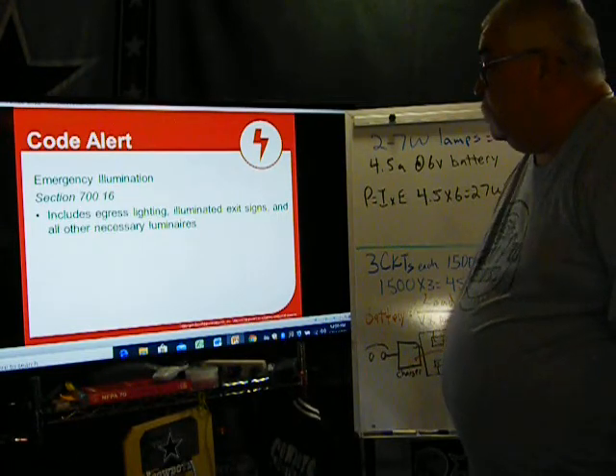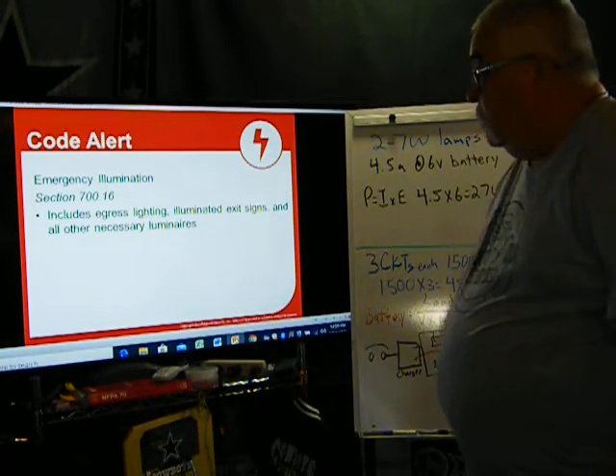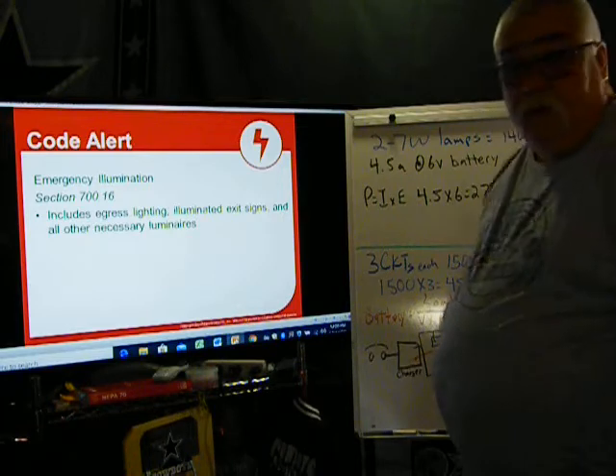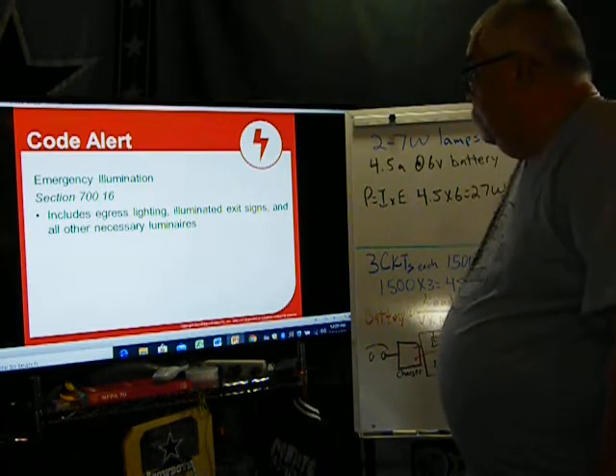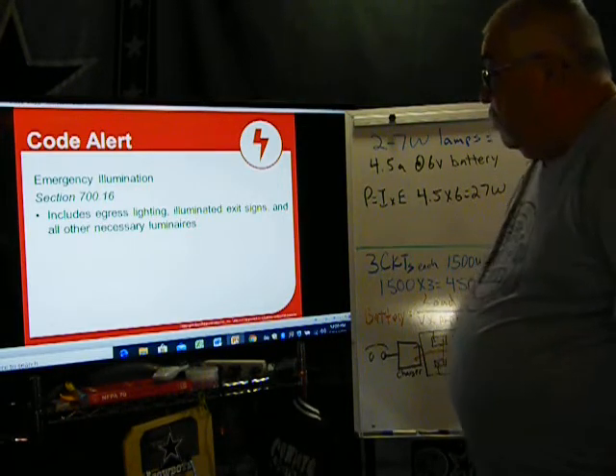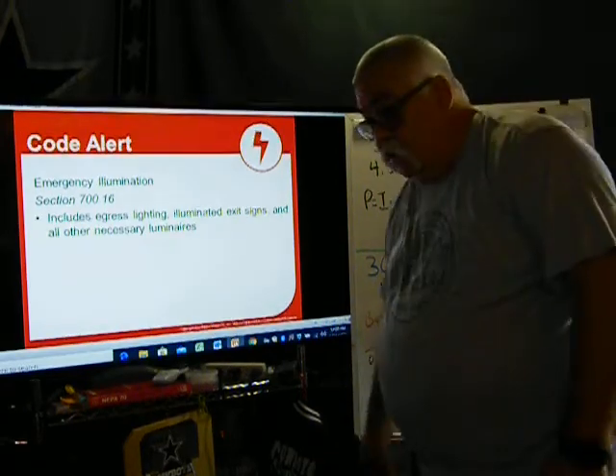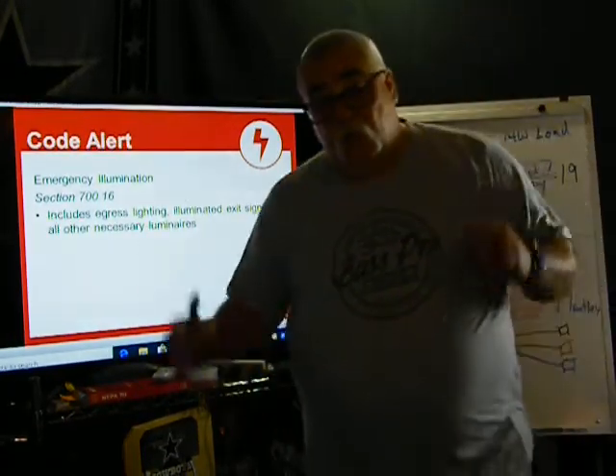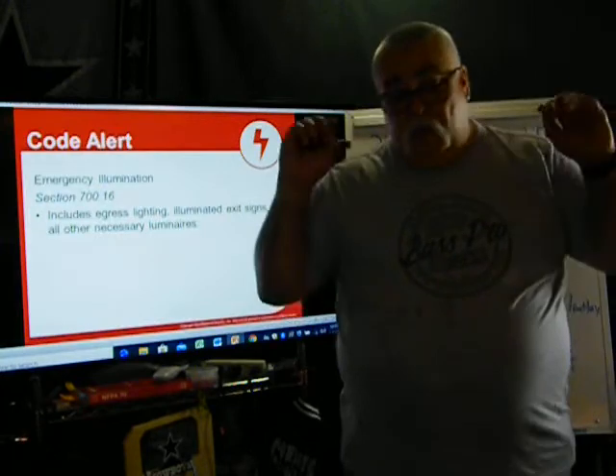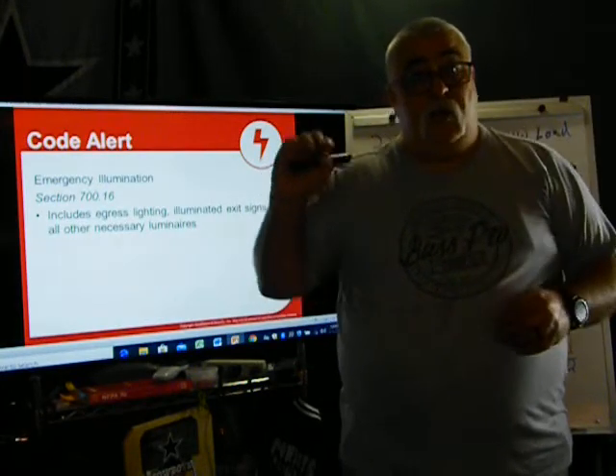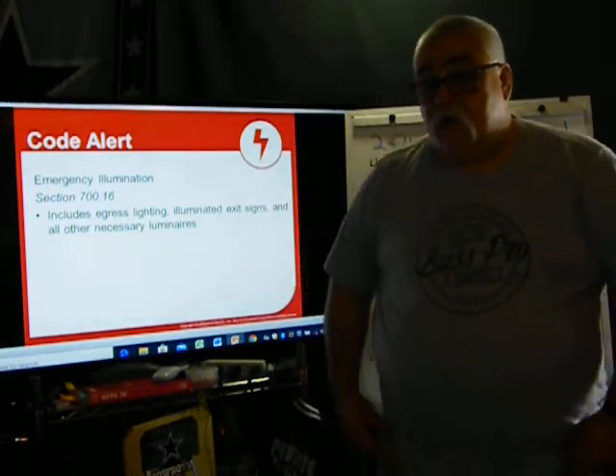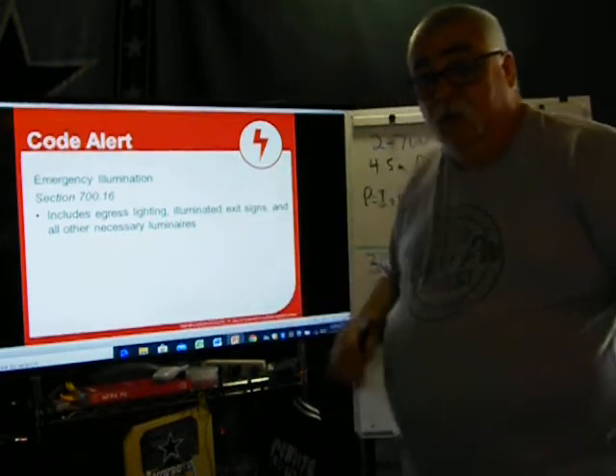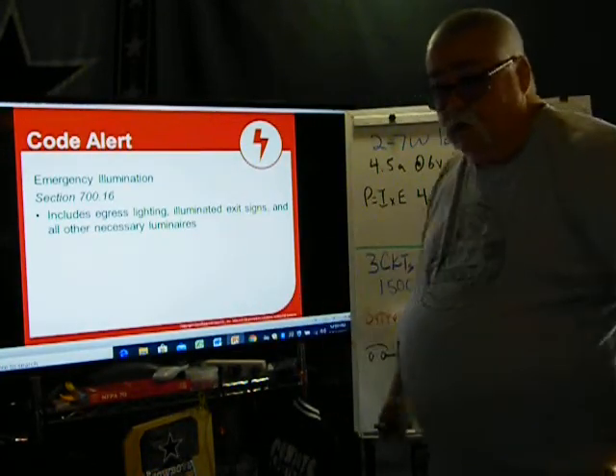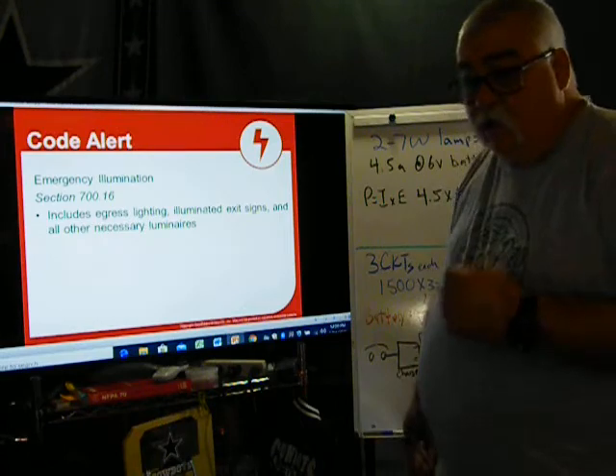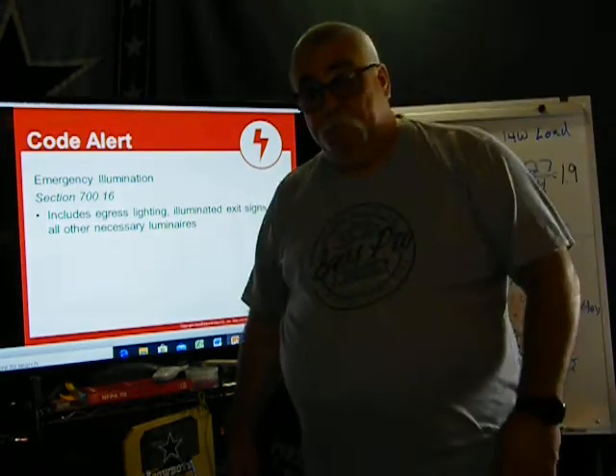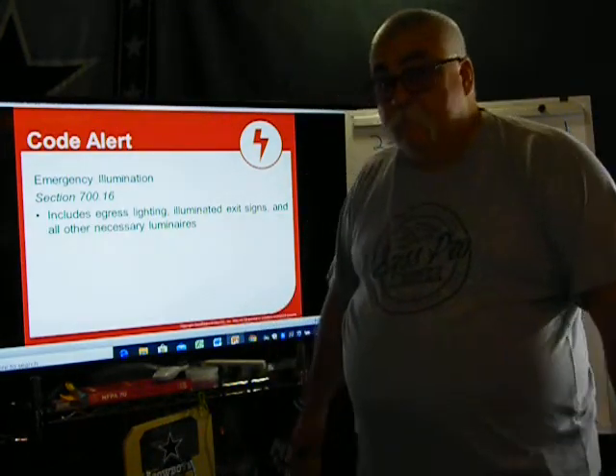Emergency illumination, section 700.16, includes egress lighting, illuminated exit signs, and all other necessary luminaires. So if you're putting in emergency lighting and you have a generator, it lights up lights in the room, lights in the hallway, and in the stairwell, and the code requires you to have this. This is egress. The egress is so you can exit the building. This is all so you can get out of the building.